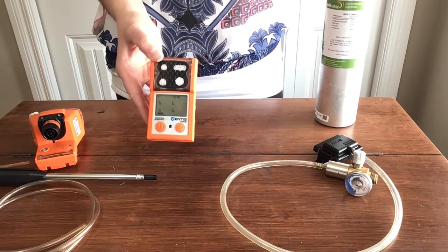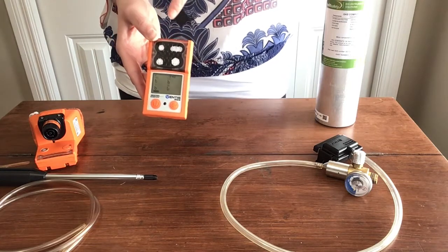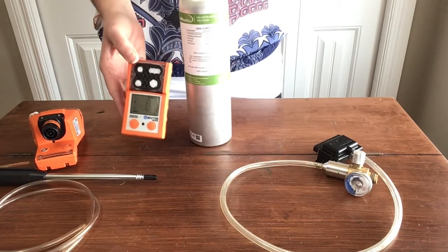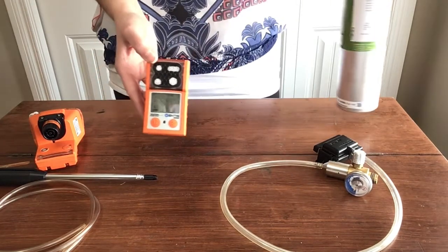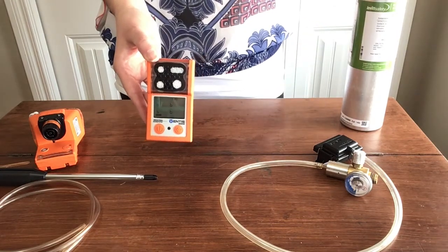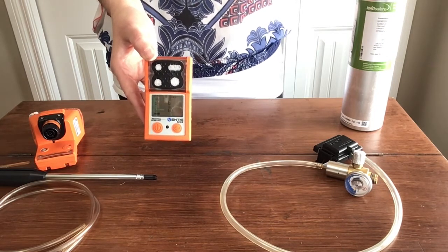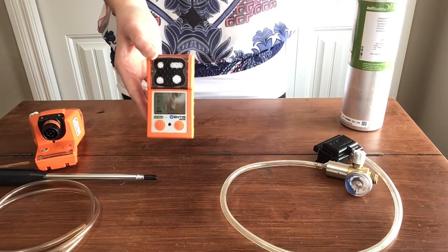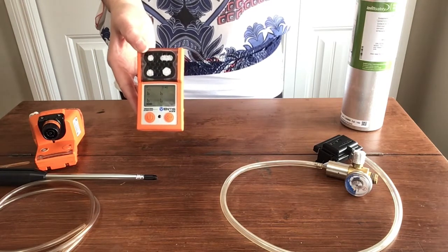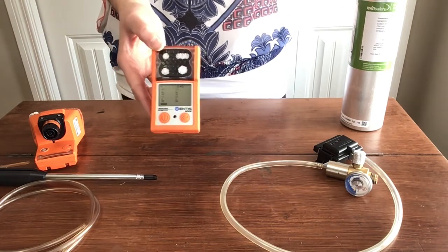During your monthly calibration, what you're doing is checking to make sure that the sensors are all reading the gas as it is concentrated in here. You are checking to make sure that your visual alarm, your audio alarm, and your tactile alarm, so the vibration, all three of those work. And it's checking the internals of the system. So we do this once a month to make sure that all of this is working when our workers take this to whatever location they're taking it to.